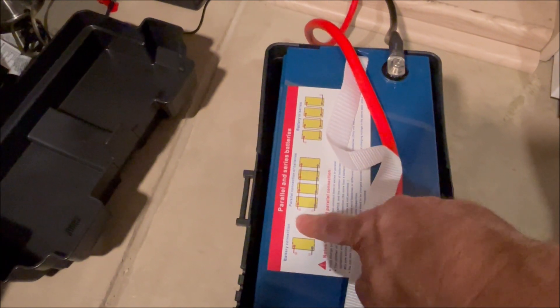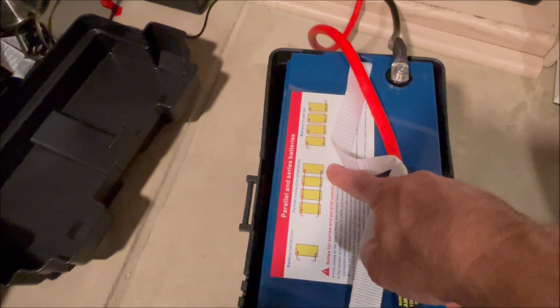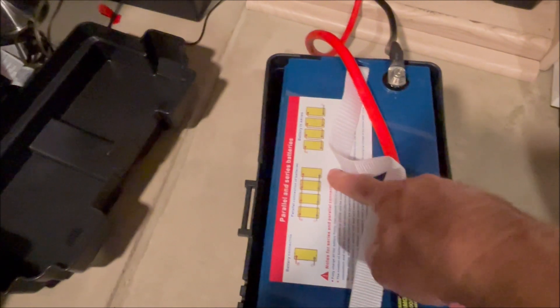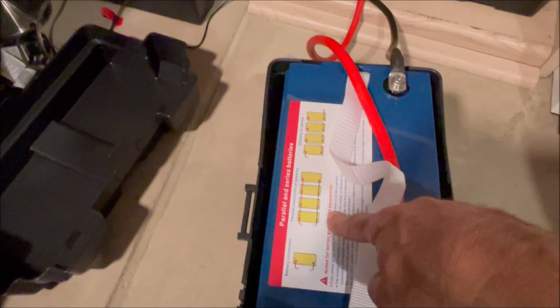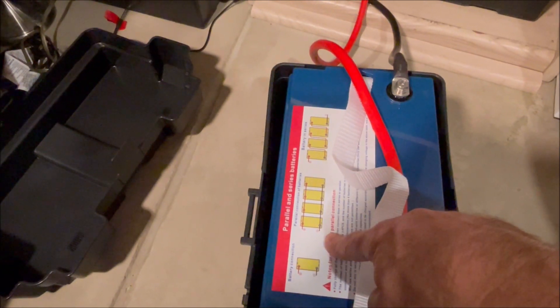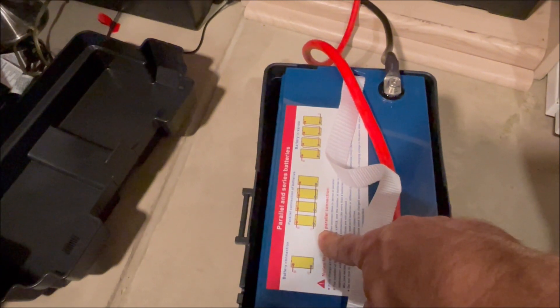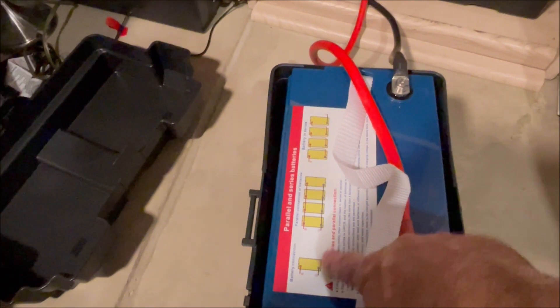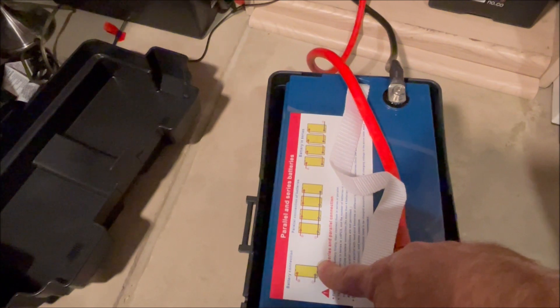So if we have a short down here somewhere with four batteries, we would output up to 800 amps before these BMSs would shut down. But if we added a fifth battery, now we're up to 1000 amps. Six battery, 1200 amps. Seventh battery, 1400 amps, and so on.